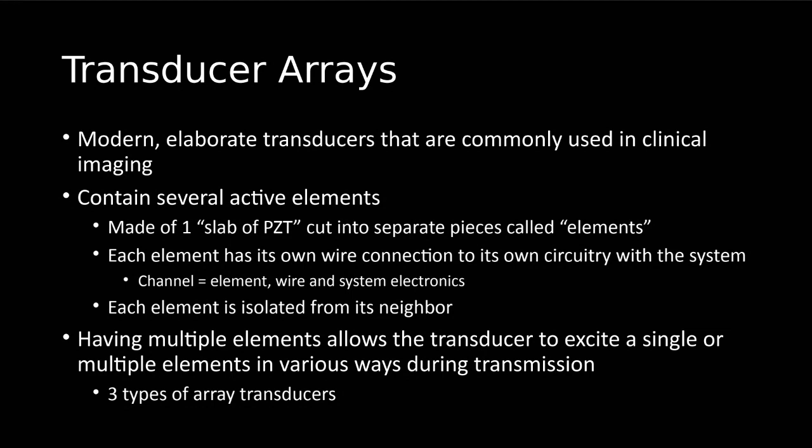Having multiple elements, so multiple pieces of PZT, is going to allow that transducer, like we said, to excite one or multiple elements in various ways or patterns when it's transmitting those sound pulses into the body.